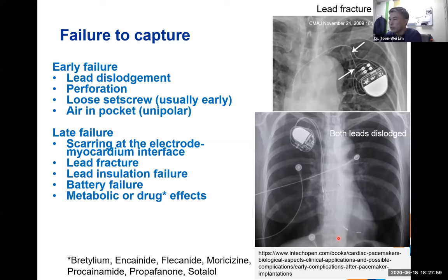In terms of late failure, there are things like scarring at the electrode-myocardial interface, and of course, lead fracture and lead insulation failures. And the X-ray up here will show you where the lead is completely broken off from where it's connected to the pacemaker. As well as things like battery failure. And of course, there's also metabolic and drug effects. And there's a list of drugs that commonly increase pacing thresholds and cause loss of capture.